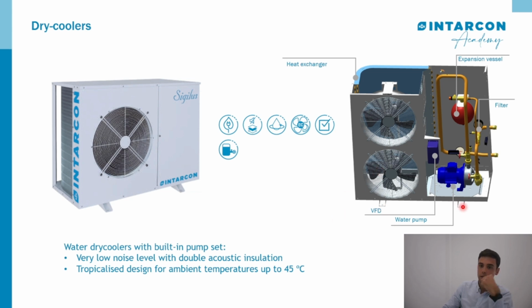They use a variable frequency drive in the water pump, so we have a variable water flow in the part of the Waterloop condenser. The expansion vessel is properly designed for the amount of water that we have inside the Waterloop system. But if the installation is larger and you have a higher quantity of water in the installation, you will have to add a new expansion vessel to adapt to the difference of thermal densities that you can have in the low temperature or in the high temperature part.